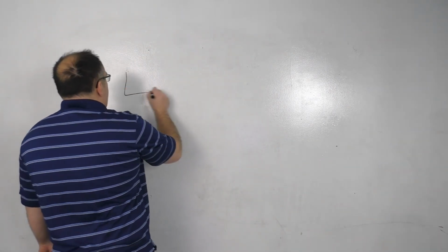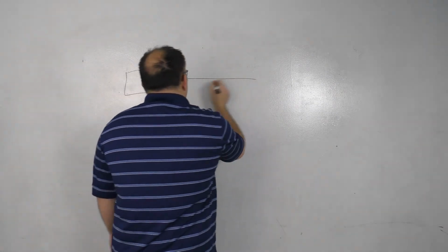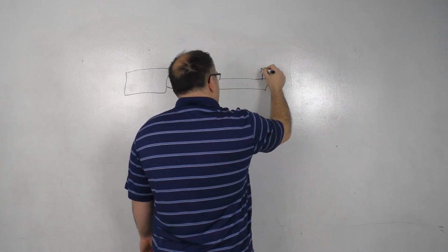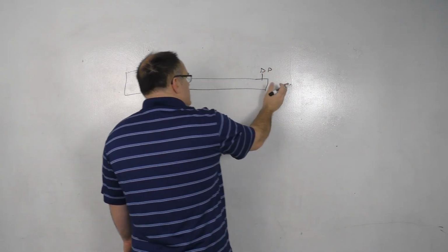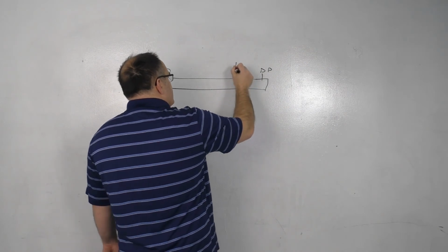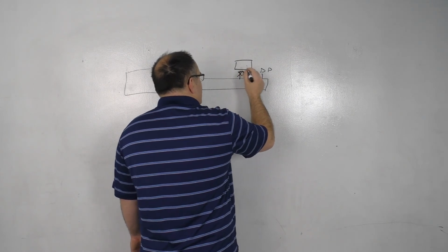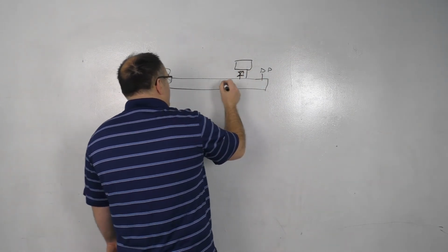All right, so for the fifth strategy, and this is not so much an optimization strategy as it is more of an experience strategy, something picked up over the years, I've seen a lot of people make mistakes on, and it's called optimal DP sensor placement. So let's say that you have an air-cooled chiller here. The general rule of thumb is that you're going to have your DP sensor down here, and once again, these drawings do not reflect how it would actually look in the field. So just forgive me for that.